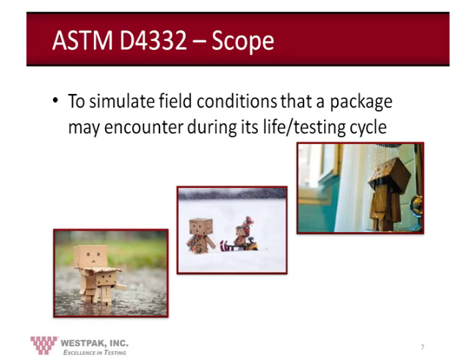There is a photo of three of our large chambers, large enough to comfortably fit six pallets side-by-side for temperature and humidity testing. The scope of ASTM D4332 is to simulate the conditions that your package might encounter during its life cycle. Your packages could be exposed to different temperature and humidity conditions such as tropical, high moisture environments, freezing conditions, or even hot, dry, and humid conditions.